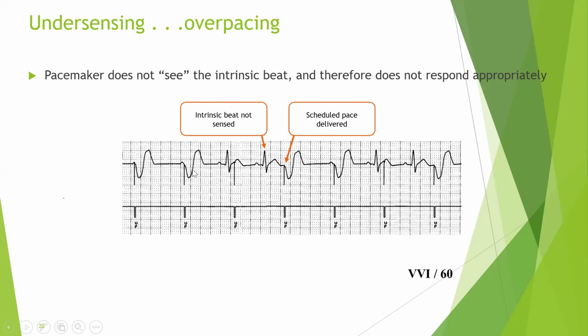You go to the second QRS. I'm talking from left to right. You see a spike, you see a QRS, and at the bottom line, which is what the pacemaker is seeing, you see V pace, indicating that the pacemaker is pacing. If you go to the third, you can see a P wave followed by a QRS. But if you look at the bottom, corresponding to that QRS, you don't see anything from the device. So the device is not seeing this QRS, which we are seeing in the surface ECG, and as a result it paced immediately after the QRS.